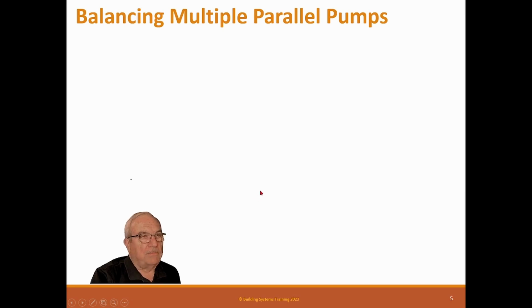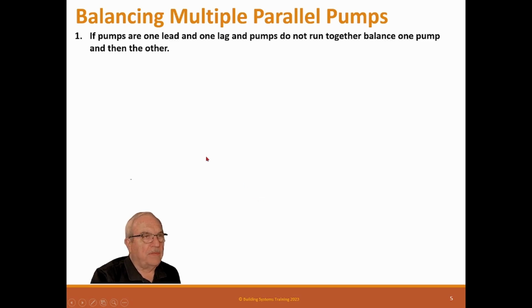So now let's talk about balancing multiple parallel pumps. Normally if you have two pumps, you have one pump as lead and another as lag. That means the lead pump runs and carries the whole load unless it fails, and then it switches over to the lag pump, giving you 100% redundancy on the project. But it is possible for an engineer to not design it that way. He can design it so that one pump carries 50, 60% of the load, and then when it gets over that, it turns on the second pump, and they're staged pumps.